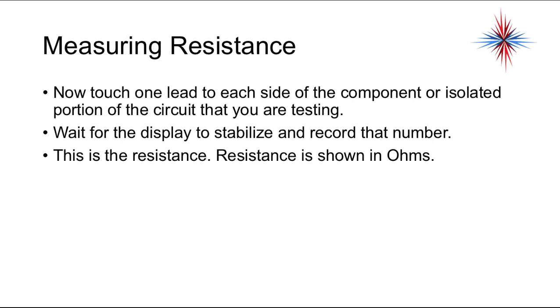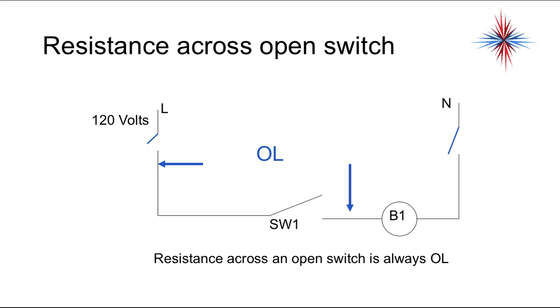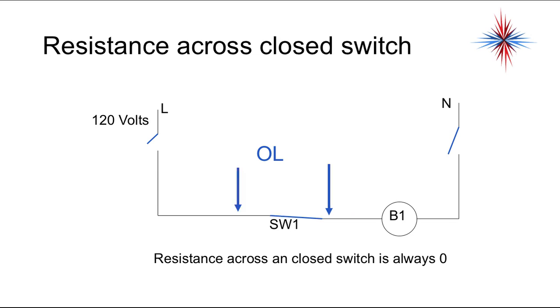Now, touch one lead to each side of the component or isolated portion of the circuit you are testing. Wait for the display to stabilize and record that number. This is the resistance. Resistance will always be shown in ohms. Resistance across an open switch will always be OL. By the way, notice the circuit breakers between L and neutral and the rest of the circuit are open. That's making sure there's no power on this circuit. But a resistance across an open switch will always be OL. Resistance across a closed switch should be 0. If you get OL, that means the switch is open internally. Nothing you can do. Replace the switch.